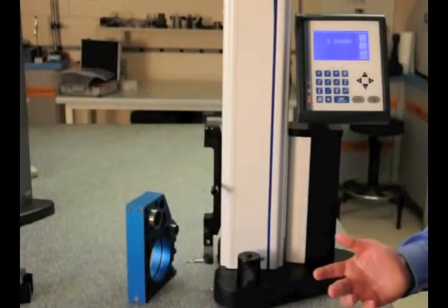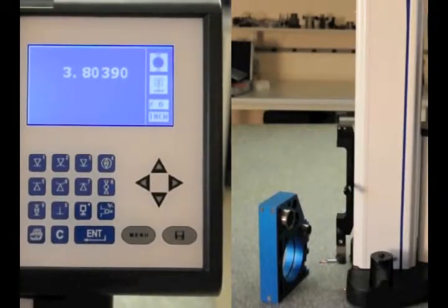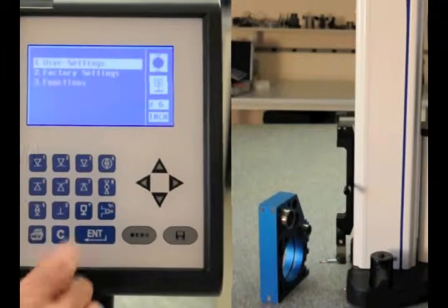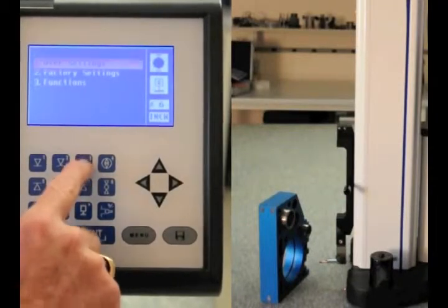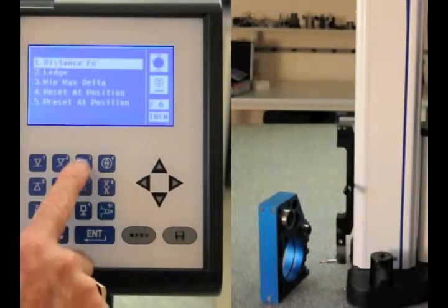We've done some basic measurements. Now we're going to go into doing a min, max, and TIR feature. To do that, we hit the menu key. We're going to select functions, number three, and we're going to select number three, min, max, delta, or TIR.